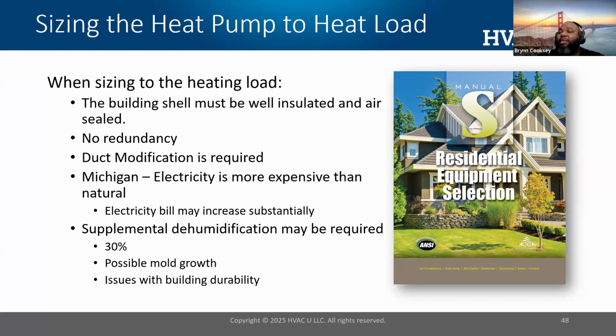You also may have to add supplemental dehumidification. If you're in, I'll say, a heating climate like Michigan is, we have more heating hours than cooling hours. Our heating loads are usually substantially larger than our cooling loads. And as a result, that heat pump, which is a two-way air conditioner, will be bigger than is needed. And if that's the case, I may not remove the moisture in the summertime. So I may need supplemental dehumidification. And according to Manual S, that number is 30%. Anytime my heating load to cooling load is bigger than 30%, supplemental dehumidification is required. Okay. If I don't have supplemental dehumidification and I can't control that humidity, I could get possible biological growth and issues with the building shell, such as durability issues.